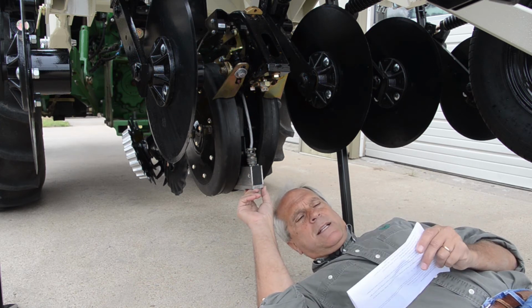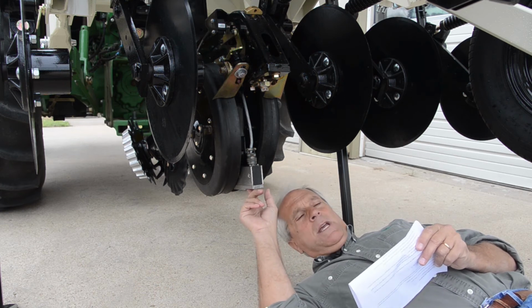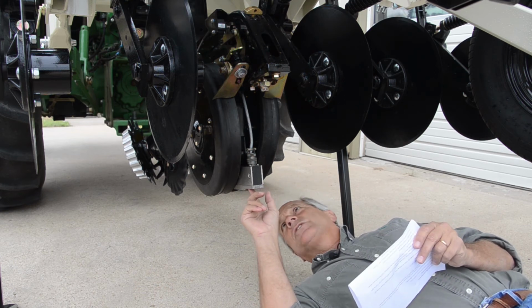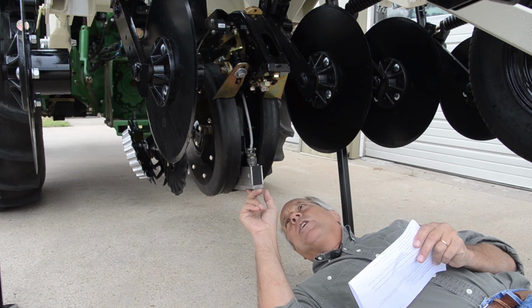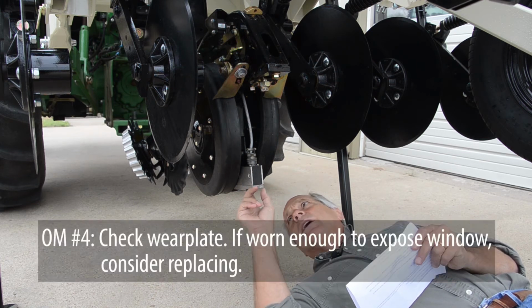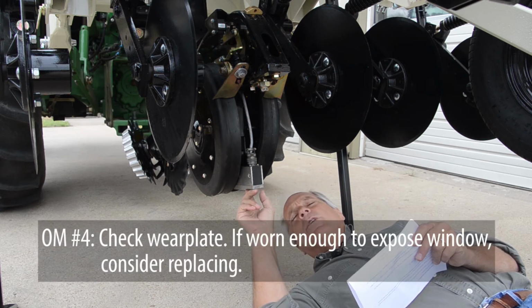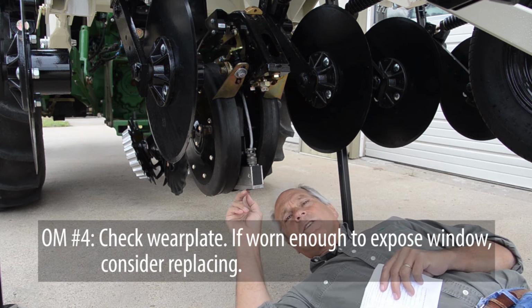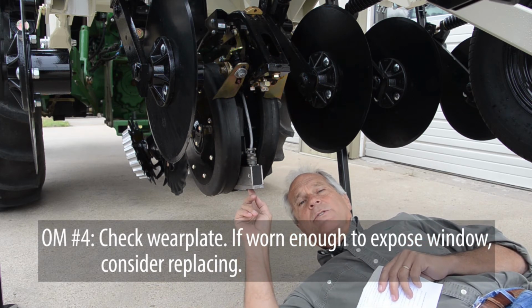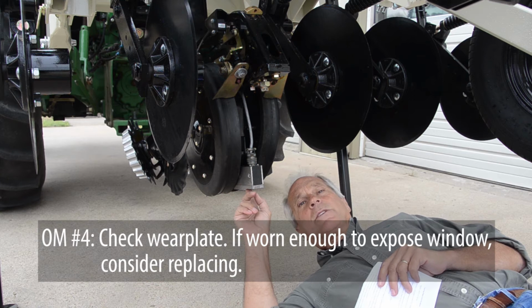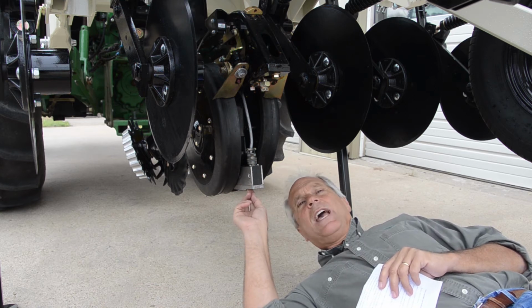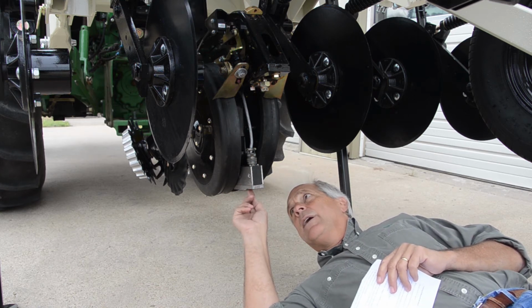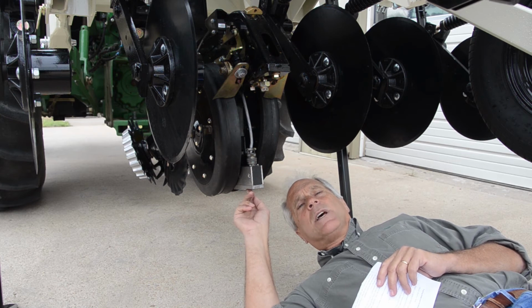And as you're inspecting that, item number 4 is to see if the wear plate and the window need to be replaced. The metal in the wear plate will actually wear faster than the window's sapphire, so the metal will wear first, which exposes the edge of the window. And it may need to be replaced if that window's exposed too much.